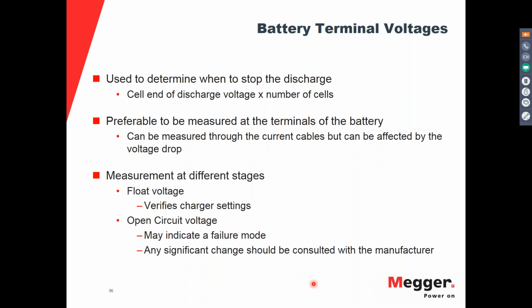Then you disconnect the charger, and there's a time that lapses between when you disconnect the charger and when you start the test, for the connections and getting everything set up. During that time the battery has been without any float voltage, it's not being charged anymore, and that is what is called the open circuit voltage. This voltage, depending on the condition of each cell, might drop a little bit or might drop a lot, and this is an indication that the battery might fail during the test. So you want to take some provisions for this to be avoided, or you can decide not to run the test because of this voltage situation.